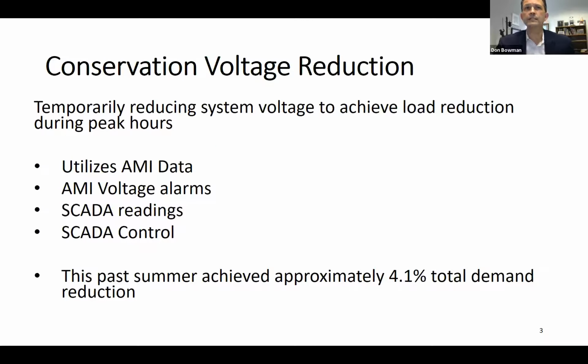Conservation voltage reduction is low-hanging fruit for Wake Electric since we're about 97% residential load. It's temporarily reducing system voltage to achieve load reduction during peak hours. We do this at substation regulators, but we've gone further with multiple downline regulators, all tied into our SCADA, with multiple zones so we can reduce voltage across every meter on our system for maximum reduction.